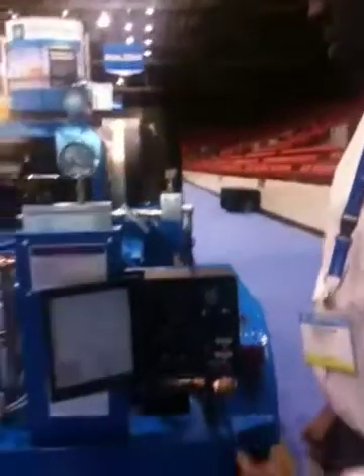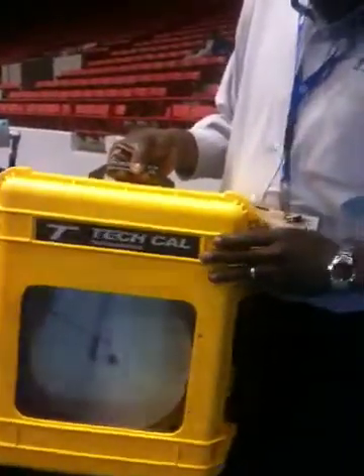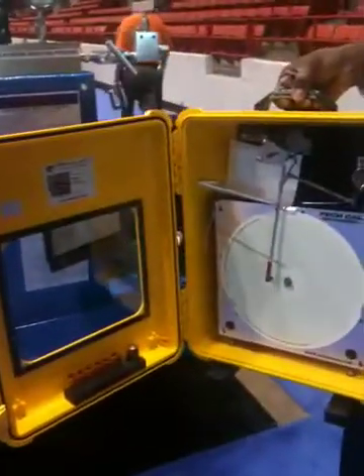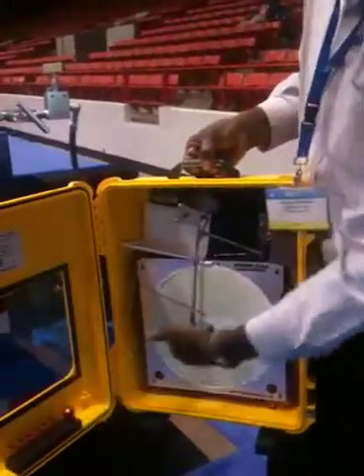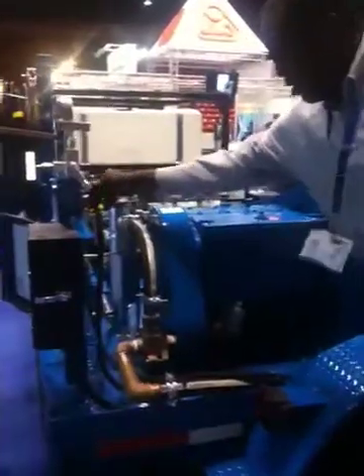This particular system is equipped with what we call a chart recorder, which allows you to pull a single chart on the system. All of our chart recorders are equipped with extra pins, battery, and extra chart paper with calibration certificates inside. It is a sealed chart recorder to keep moisture out, and it has a line coming from the rear of the control panel with a valve that you can either turn on or off.